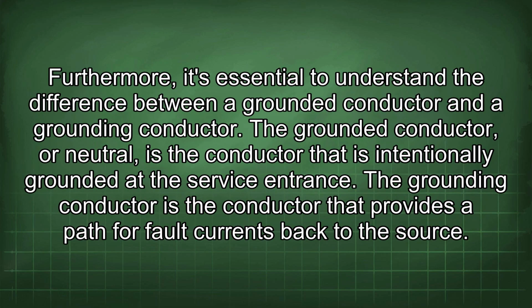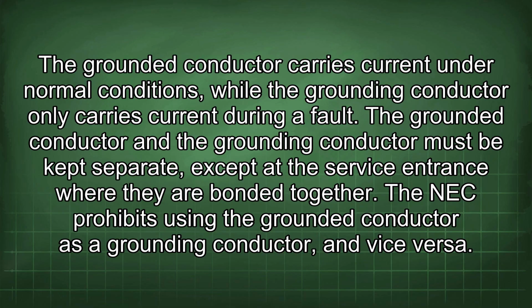Furthermore, it's essential to understand the difference between a grounded conductor and a grounding conductor. The grounded conductor, or neutral, is the conductor that is intentionally grounded at the service entrance. The grounding conductor is the conductor that provides a path for fault currents back to the source. The grounded conductor carries current under normal conditions, while the grounding conductor only carries current during a fault. The grounded conductor and the grounding conductor must be kept separate, except at the service entrance where they are bonded together. The NEC prohibits using the grounded conductor as a grounding conductor, and vice versa.